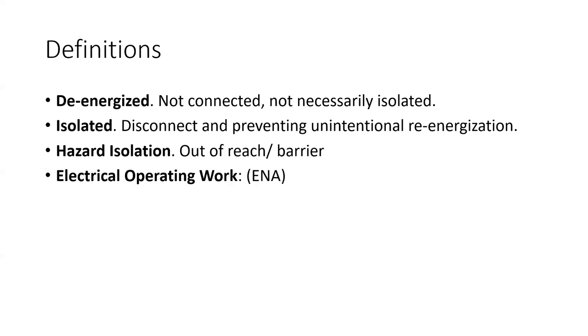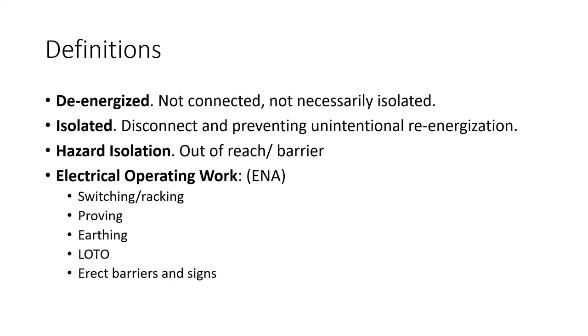And if we look at the ENA standards, the definition of operating electrical work is quite interesting because it says it's switching, in other words, disconnecting the power, proving, so it's testing that you don't have any power there, and then earthing, closing earth switches or applying earth cables, and then locking out, tagging out, and perhaps erecting barriers and signs. And interestingly, these are also the electrical isolation principles specified in AS 4836 that we'll be talking about today too. AS 4836 is the Australian standard on safe working on or near low voltage electrical installations and equipment.